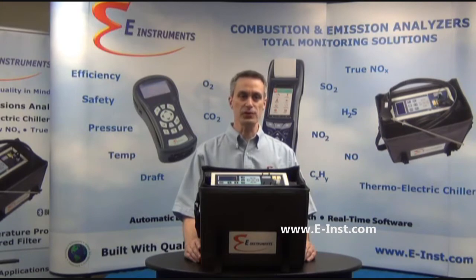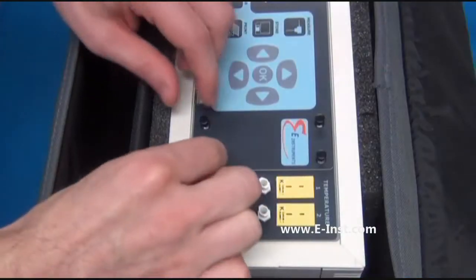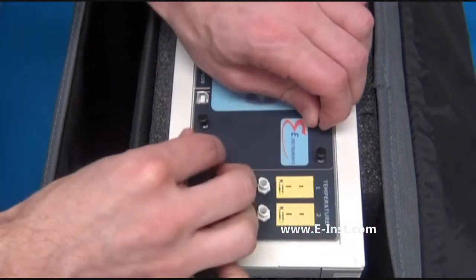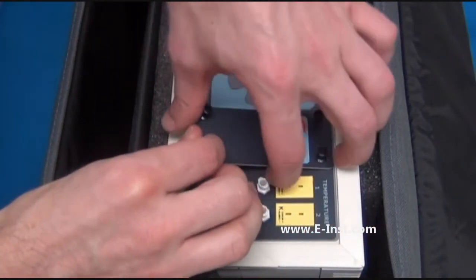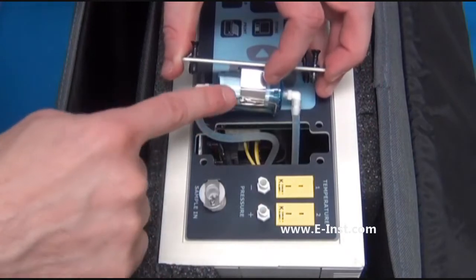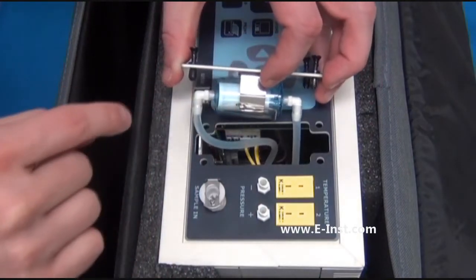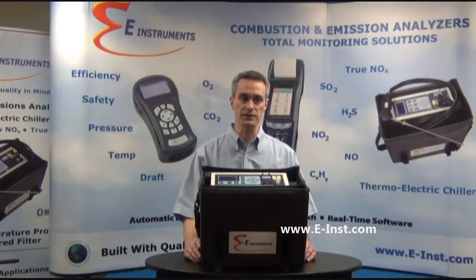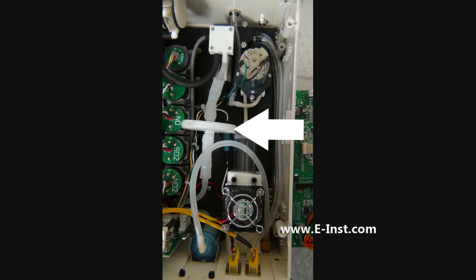Take a look at the line filter that collects dust, ash, and particulates from the stack gas. You can access this filter by pulling 4 black captive screws and pulling out the filter panel. The line filter gets dirty from the outside in, so you can easily see how dirty it is at all times. There's also a disposable condensation disc filter inside the analyzer that collects any residual moisture that might be in the stack gas after it passes through the chiller.